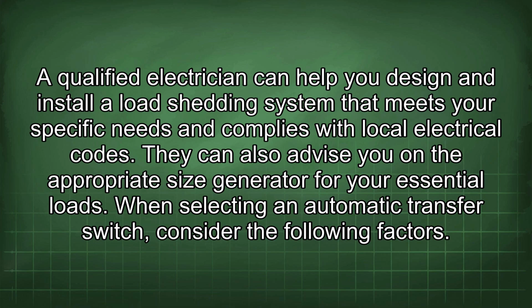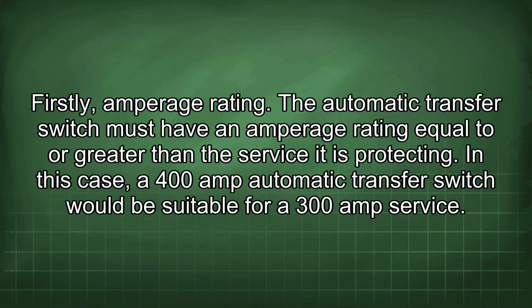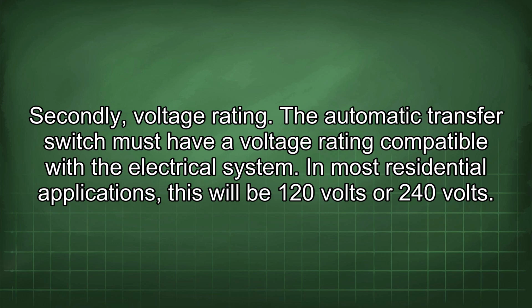When selecting an automatic transfer switch, consider the following factors. Firstly, amperage rating. The automatic transfer switch must have an amperage rating equal to or greater than the service it is protecting. In this case, a 400 amp automatic transfer switch would be suitable for a 300 amp service. Secondly, voltage rating. The automatic transfer switch must have a voltage rating compatible with the electrical system. In most residential applications, this will be 120 volts or 240 volts.